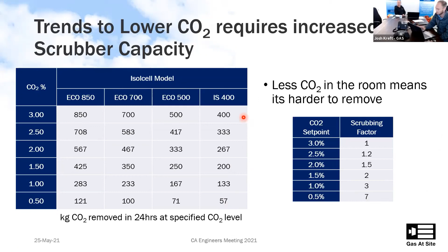Okay, so let's tackle this second example by variety. We've got our 4 rooms of Goldens that we're storing at 2.5% carbon dioxide. These 4 rooms of Goldens will be producing 100 kilograms of carbon dioxide, half the amount that was produced in our previous example because it's only 4 rooms. We're storing at 2.5% carbon dioxide, so using our table, we know we can multiply by 1.2 to see our nameplate scrubbing capacity required. So we need 120 kilograms to manage our golden rooms.